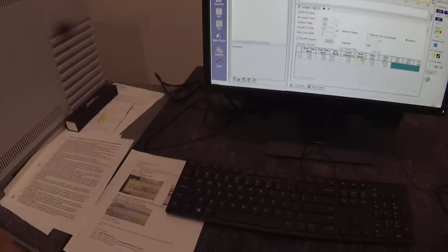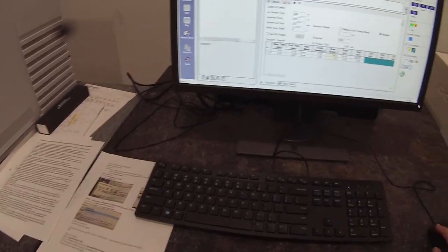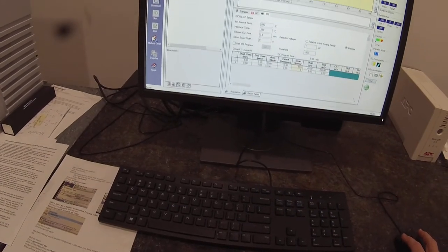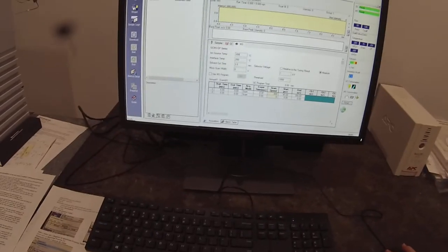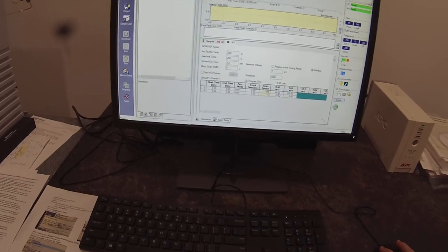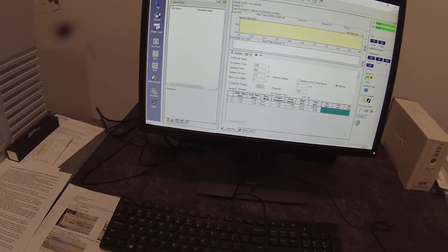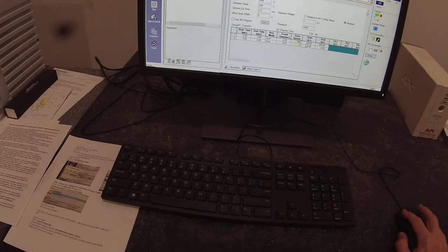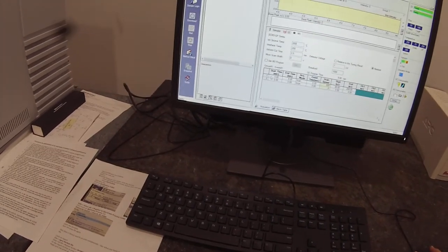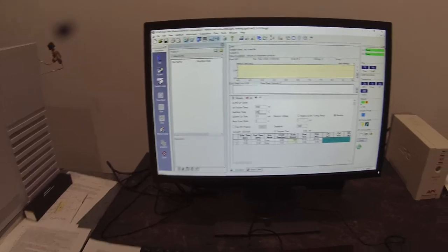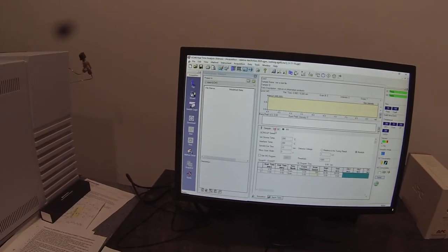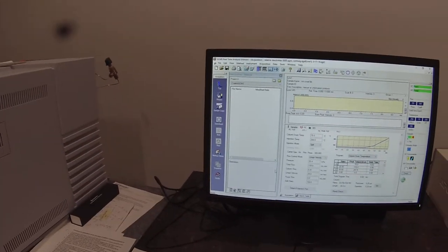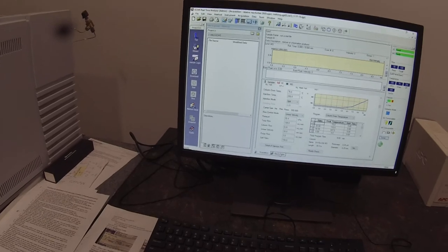So we're actually going to collect data from 4 minutes to 9 minutes, between 40 AMU, atomic mass units, this is the mass over charge ratio, and 200 atomic mass units, which is where our compound lies. The rest of this is not that important, but we need to know that we're scanning from 40 to 200 atomic mass units and between 4 and 9 minutes. And we need to know the interface and ion source temperature. All of this information is available from the data file at the end. So that's the method that we're running.